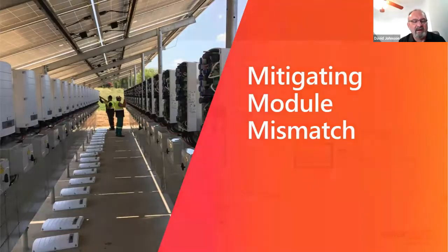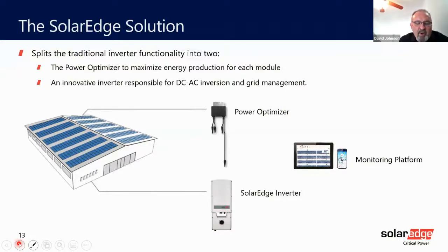So how do you mitigate module mismatch? SolarEdge's approach is to split the functionality of a traditional inverter into smart electronics attached to every module, called power optimizers, which maximize power generation per solar panel, and a smart inverter that handles conversion from DC to AC. The smart electronics on each module turns them into smart modules that can communicate their production, allowing users to benefit from module-level monitoring.